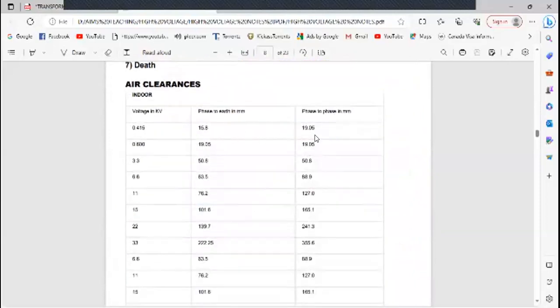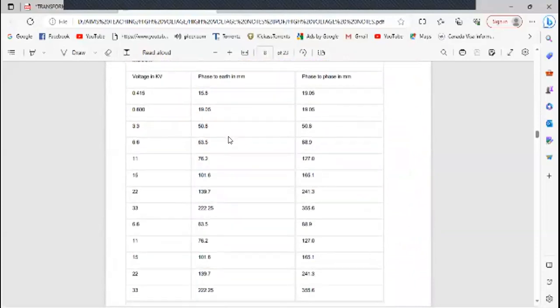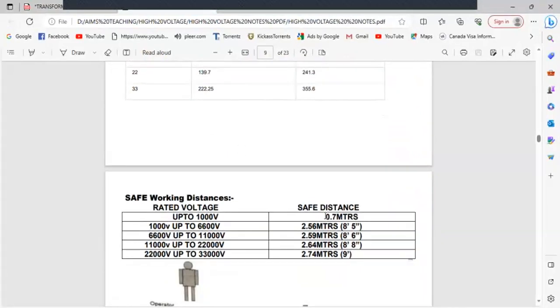This is for this thing, one minute. So up to 1000 volts, greater than 1000 volts was high voltage, 0.7 meters. Even if you say half a meter, if you put your hand very close to this, you are certainly going to have arcing and get electrocuted, because it's going to jump across to you, since you are grounded through your shoes, even though you have safety shoes with rubber soles.